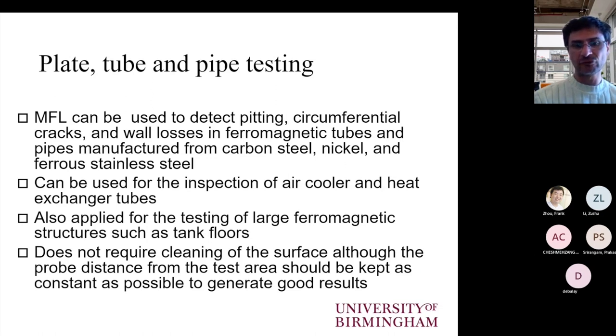The majority of the applications, of course, relate to plate, tubes, and pipes, as I mentioned earlier. It is very common to inspect air cooler and heat exchanger tubes using this method. So we push the magnetic flux leakage probe through the tube, and then as we retrieve it, we take the measurement and we look at the signals in order to see whether there is any pitting or general corrosion or erosion that has affected these tubes. The same can be done for pipes, but it is also feasible to do the inspection from the outer layer, provided that the wall thickness is not excessively great.